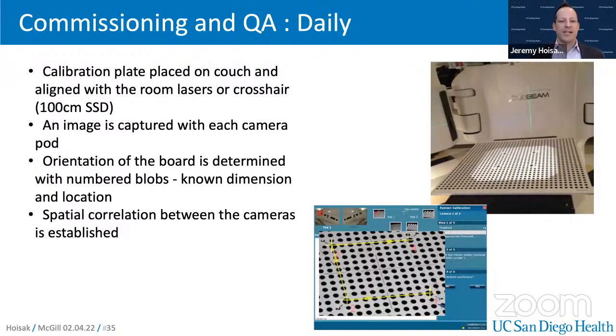For daily commissioning, we use this calibration plate. This is placed on the LINAC couch. The light field is used to illuminate it. And then there's software. This is AlignRT software, where we image these known blobs, where their orientation and distance from each other are known. The software can then establish a spatial correlation between cameras using this calibration plate. So all three camera pods are looking at the same plate, and this allows us to ensure that they are correctly calibrated.